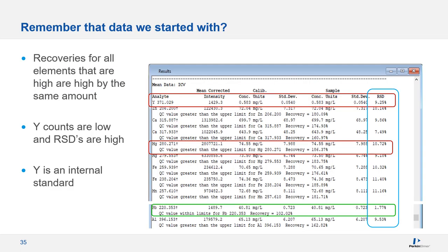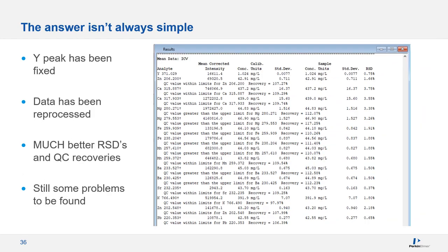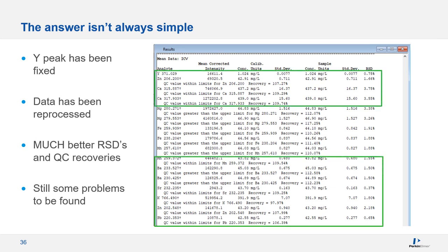Think back to that bad QC data we saw earlier. You may have noticed that all of the elements that were reading high were off by approximately the same amount. When looking again at the RSDs, we saw that the RSDs for the yttrium internal standard is 9% too. This is bad. We saw that yttrium was one of the elements that had the peak position off, and the right background point was up on the shoulder of the peak. It turns out that the difference between lead, which had good RSDs and good QC recoveries, and everything else, was that lead didn't use yttrium as an internal standard. So, now we've fixed the yttrium peak, and the background point positions have been corrected, and the reprocessed data looks much better. RSDs are now all under 4%, with most of them under 2%, and the QC recoveries are much closer to what we would expect. Unfortunately, they aren't all passing, so there are still some issues to be uncovered. Sometimes there's more than one mystery to be solved.